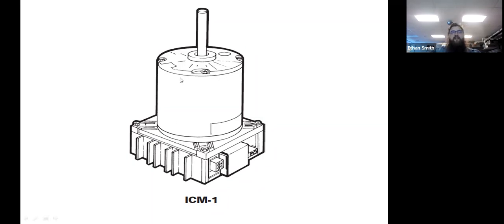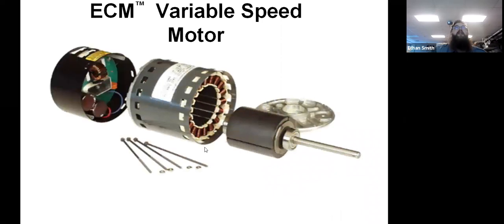So these were the first foray in the residential market into variable speed blower motors. They worked, but they were extremely susceptible to moisture damage, and they tended to not live very long because they had this open controls box here. But they very rapidly moved on to the ECM 2.3s, which is what we see out in the field today. This is just one of those things broken down. And so that actually has a 3-magnet rotor on ball bearings, and then we've got our 3-phase motor windings around it, and then we have a frequency drive on the back of this guy.